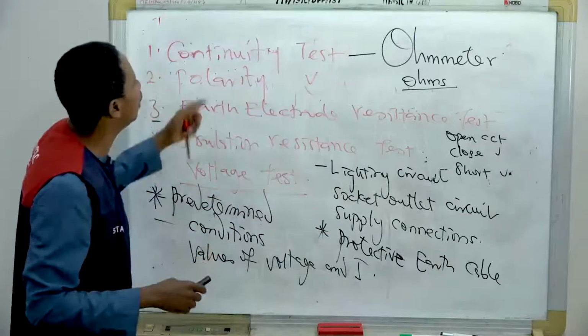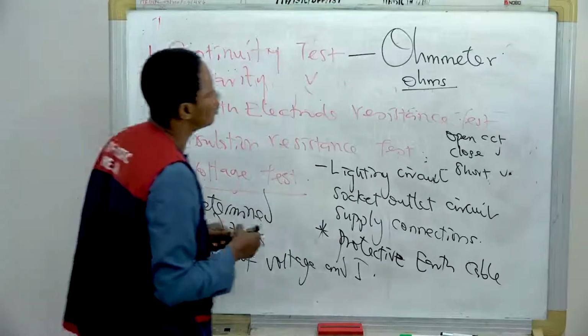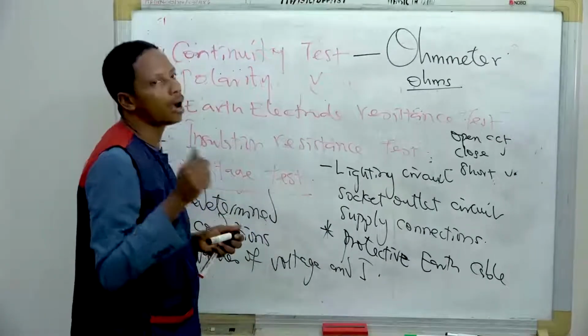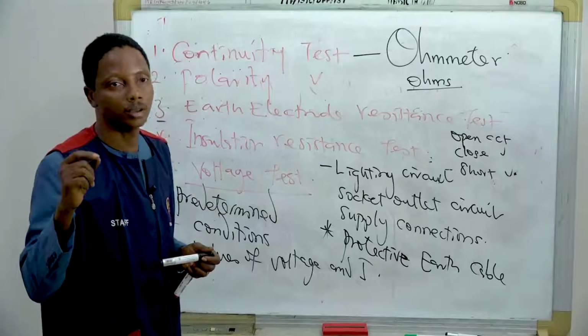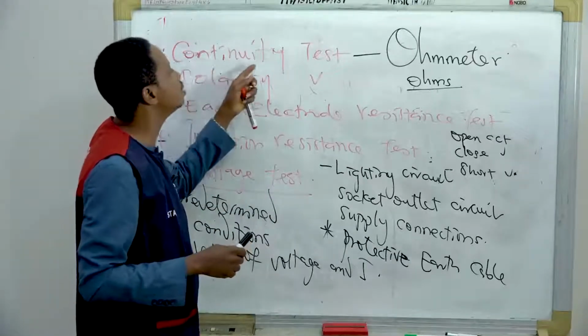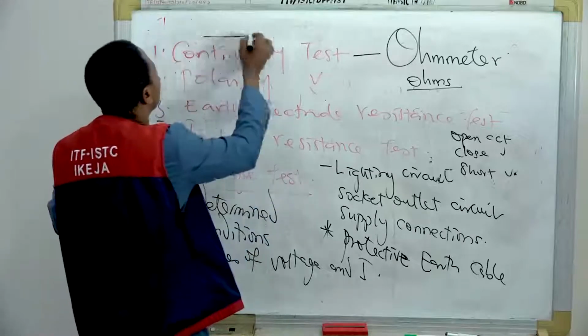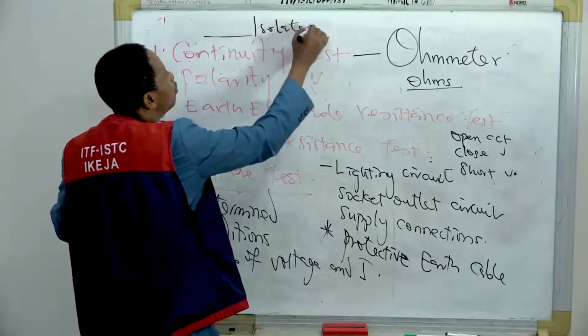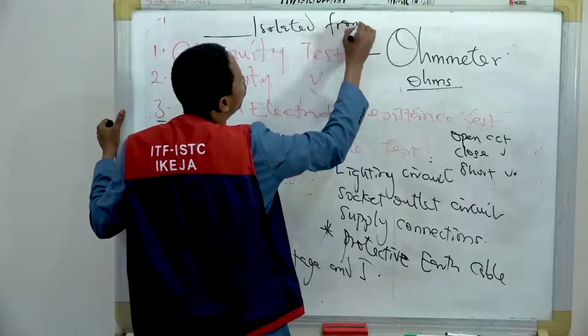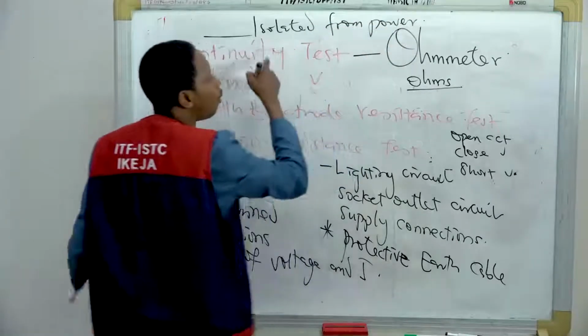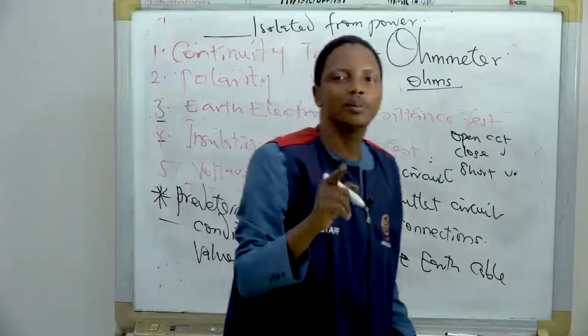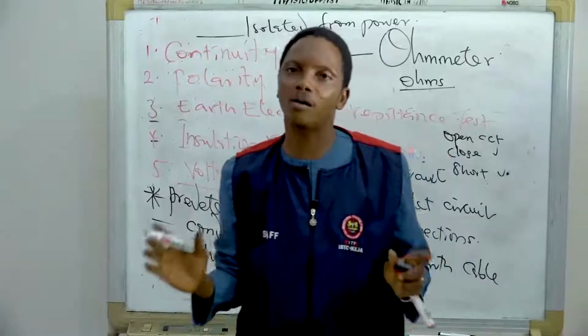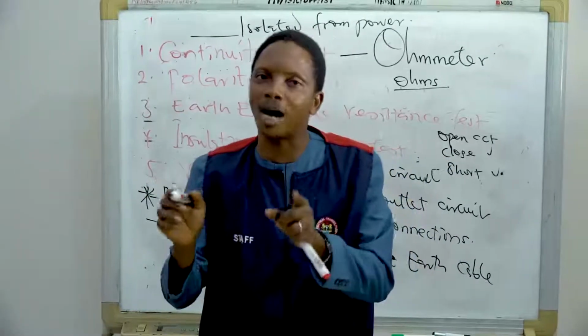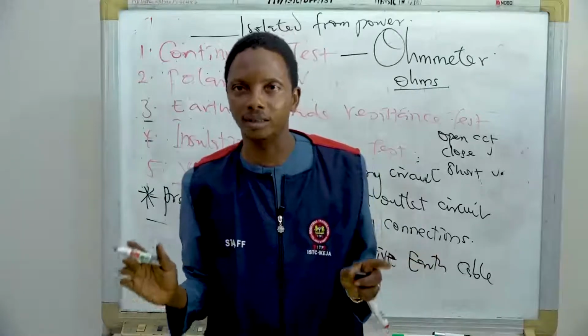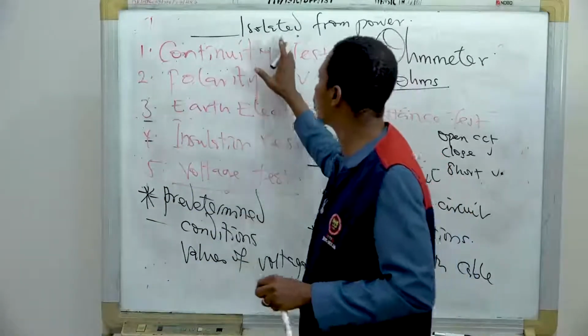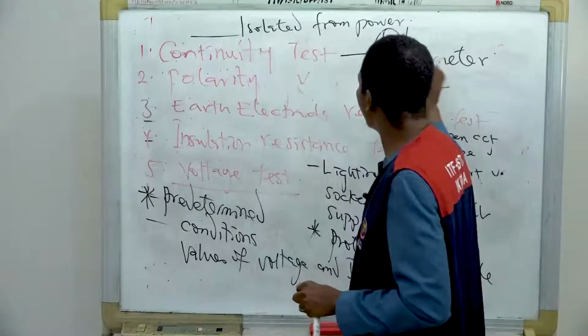Continuity test. Then we move to polarity test. Let me reaffirm something so that you will know. To carry out continuity tests, the circuit must be isolated from power. Because the presence of power in the circuit means current is flowing. The moment you put your meter on it, it will burn your measuring instrument. So make sure that the circuit is off and you use ohmmeter for continuity test.